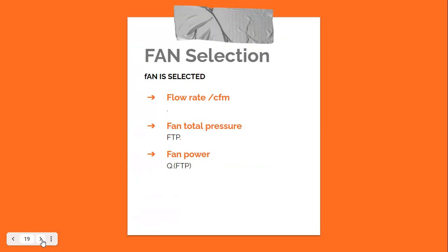In summary, to calculate the external static pressure or fan total pressure: have the friction charts and duct dimensions available, know the flow rates, and use the ASHRAE Handbook where fitting loss coefficients are tabulated. Calculate the fan total pressure, multiply by the flow rate to get the fan power, and this completes the introduction to fan selection and how external static pressure and fan total pressure are determined.